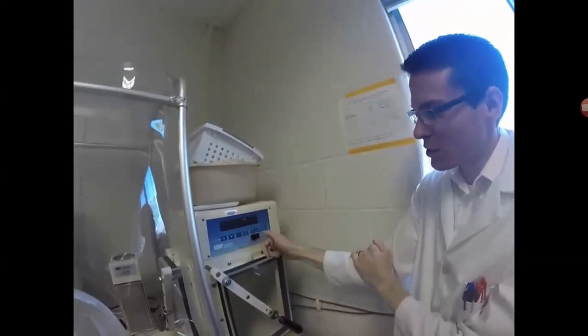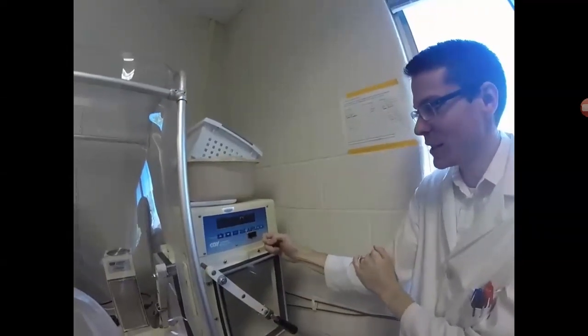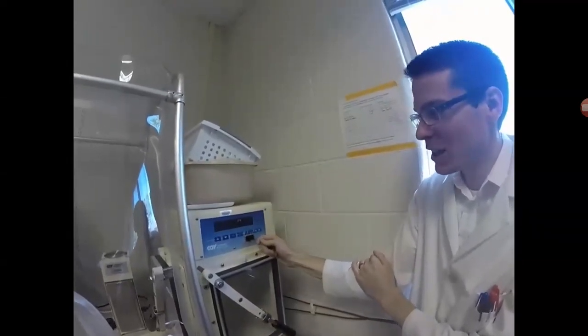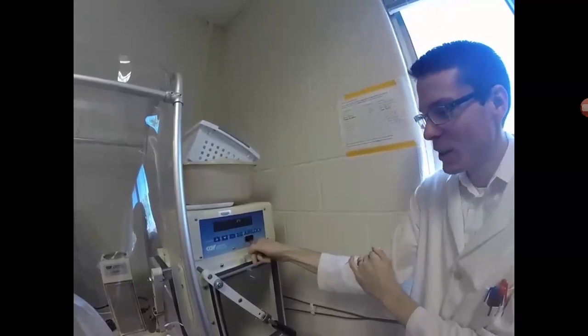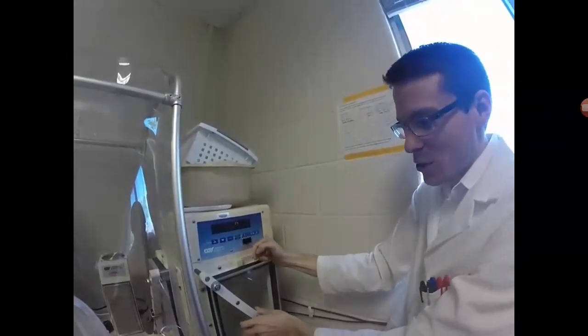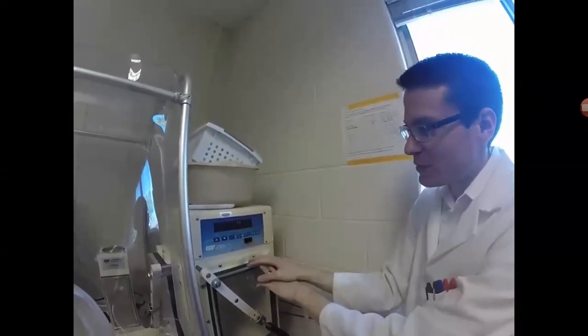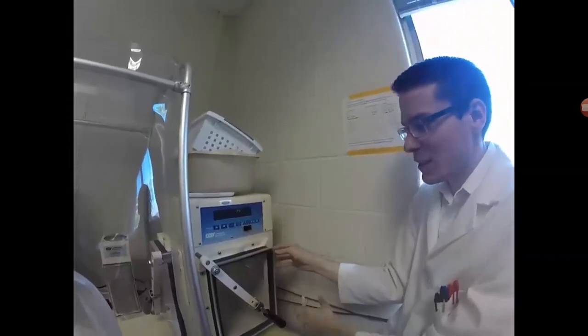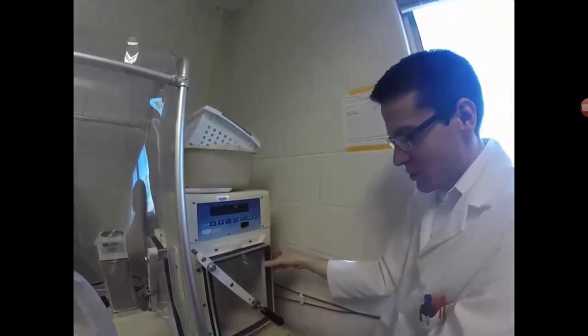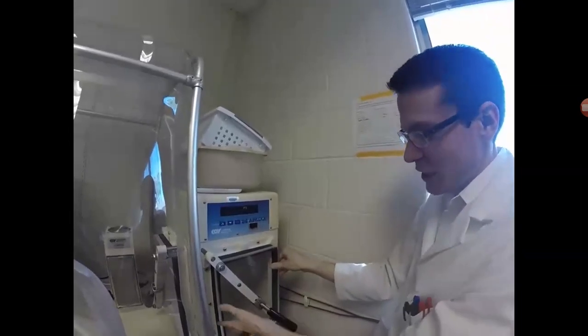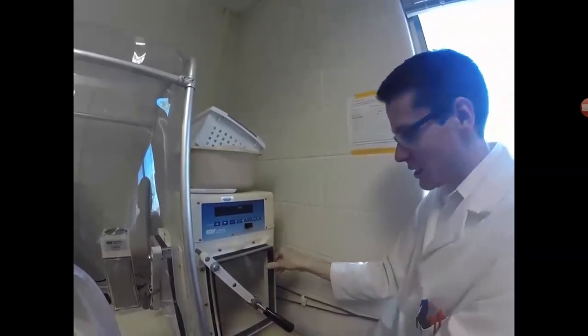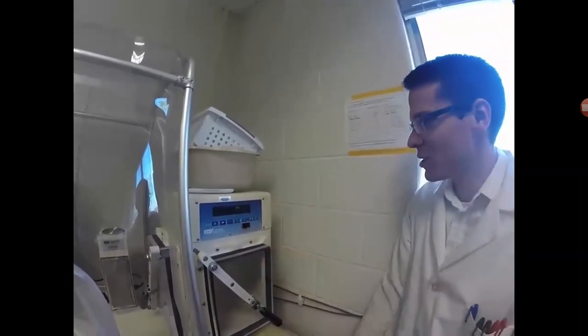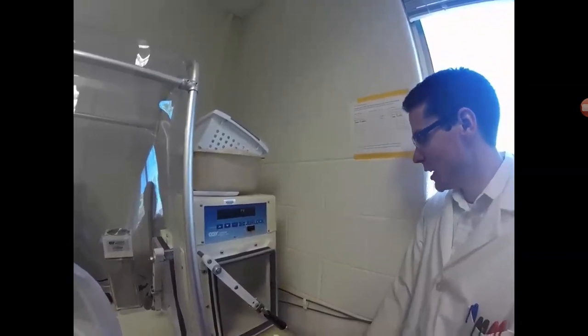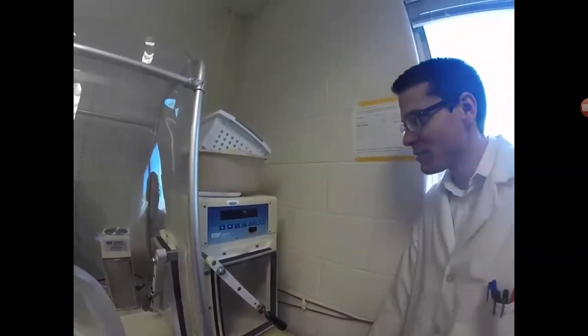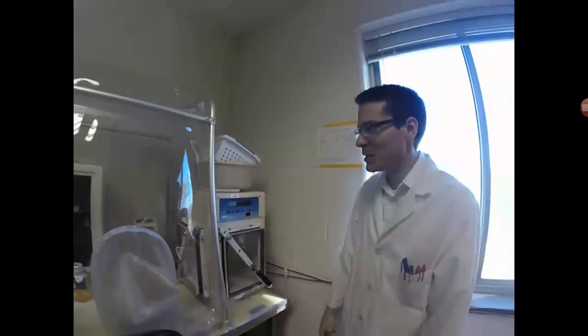So if you have a partial vacuum pull, let's say 10 inches of mercury, you're going to have to shut the thing off, turn it back on, go to manual mode, and then purge it with a purge gas in order to get the door open. Because even a vacuum of a few inches of mercury on this thing won't allow you to open the door. So the door will be essentially shut. You won't be able to move it at all, even if you open the latch. So yeah, that's good. Other than that, I think that's the other things we can do.